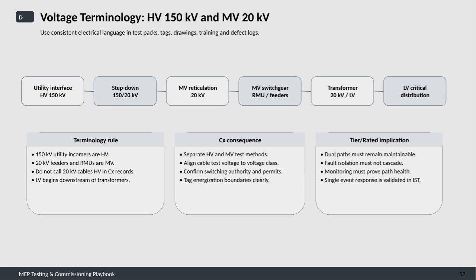The slide also highlights the typical utility interface, showing flow from the 150 kV HV utility interface through the step-down transformer to 20 kV MV reticulation, then to MV switchgear like RMUs and feeders, and finally down to LV critical distribution. From a terminology rule perspective, the takeaway is to strictly differentiate HV and MV components and ensure all test packs, tags, drawings, training, and defect logs reflect this consistently.